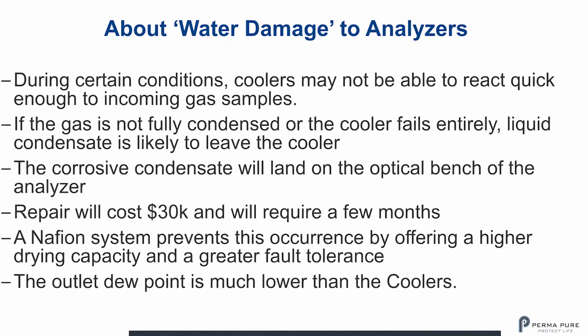So this is the real reason why Nafion tubing dryers save money for CEMS operators, because these conditions can occur. Over time, if you're running multiple sites, we have a system integrator that actually builds in Nafion gas sample dryers ahead of the coolers as a preventative measure, and they found that the dryers pay for themselves. They've done the statistical analysis and show that they prevent damage to the analyzers enough to make it worth putting them in addition to the coolers, not just instead of.